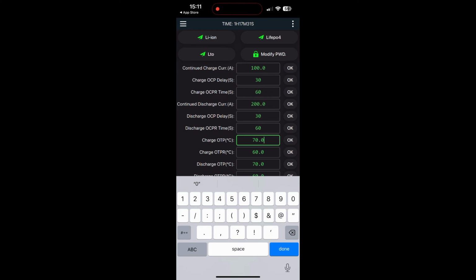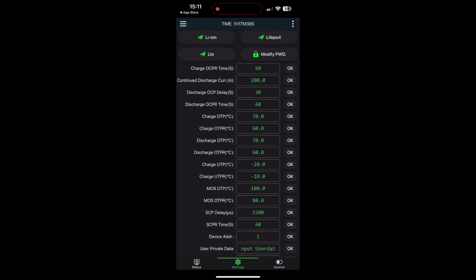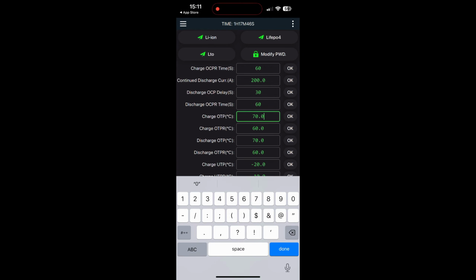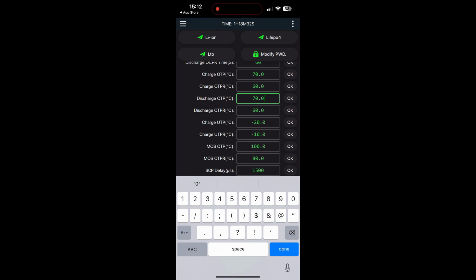charge over temperature protect. That basically means that the BMS will allow the cell to get to 70 degrees, and if it gets to 70 degrees, it will stop charge going into the bank. The two temperature probes on the BMS are what measure the temperature. If any one of the cells gets to 70 degrees, which I've never seen before, it'll stop charge going in. Charge OTPR, the over temperature protect reset, will allow charge to start going back into the cells once all of the cells are below 60 degrees. Same as the discharge OTP, discharge over temperature protect: if any one of the cells gets to 70 degrees during discharge, it will disconnect the BMS. Once all the cells are below 60 degrees, it'll allow discharge to continue.